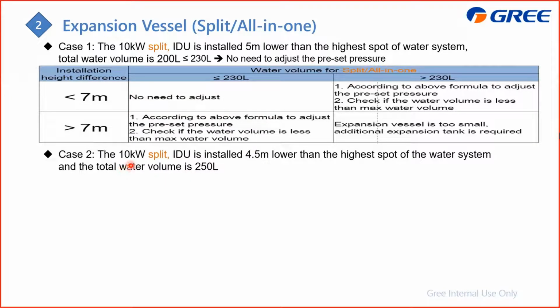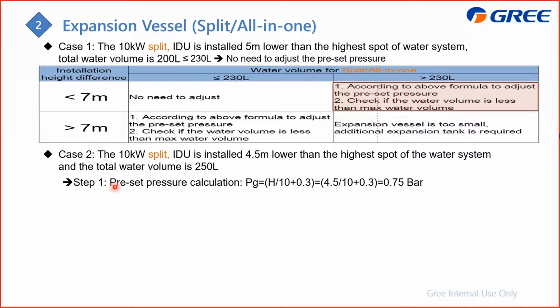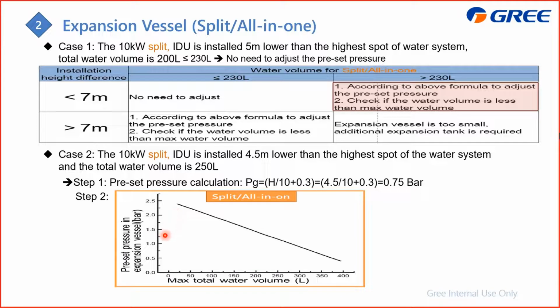The second case is also the same 10 kilowatt split type, and the indoor unit is 4.5 meters lower than the highest spot, and the total water volume is 250 liters. According to this table, it belongs to this part, which means according to the graph you need to adjust the pressure, and the target is according to this formula. You can get 0.75 bar, and from this graph you can find that at 0.75, the total water volume can be up to 325 liters, which can cover this 250, which means this is okay.